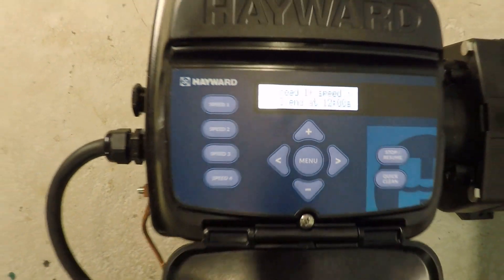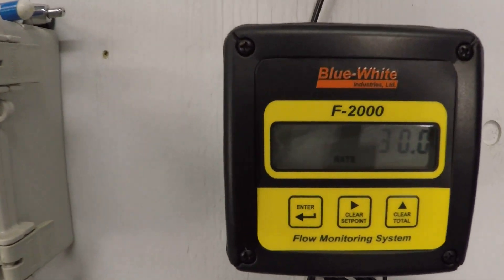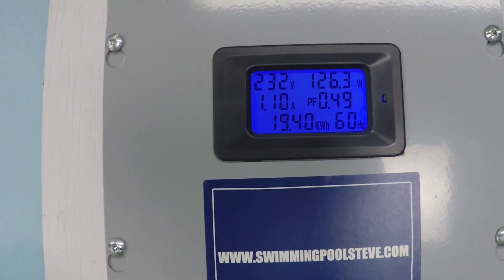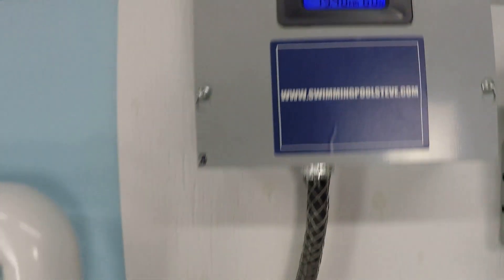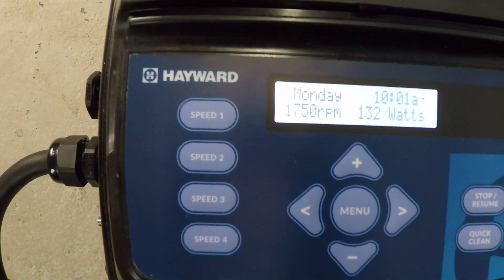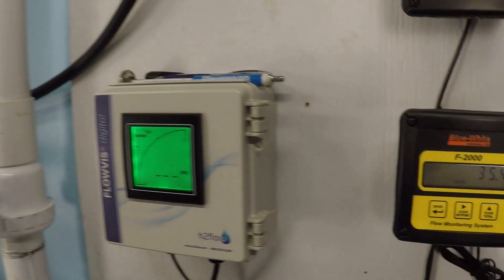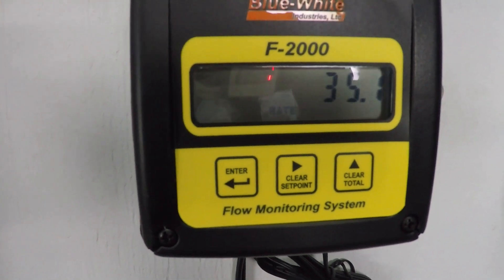At 1,500 RPM: 30 gallons per minute, 126.3 watts, 1.1 amps current draw. Up to 1,750 RPM: 35.2 gallons per minute.